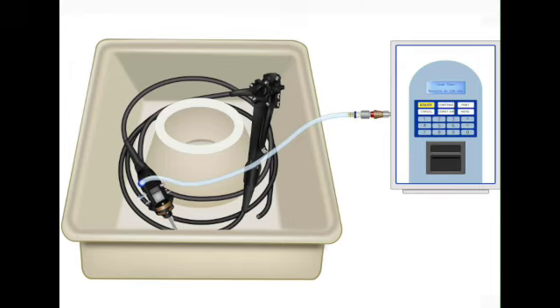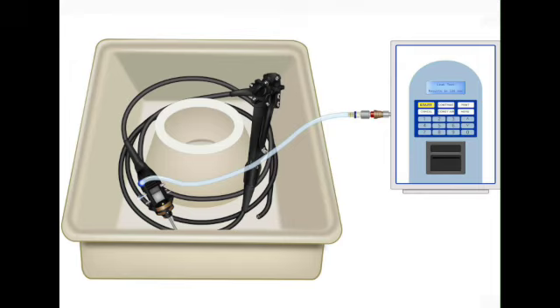Okay, seems straightforward enough. Well, here's a detail that often trips people up. It's about how you position the scope. Positioning? Yeah. If you put the scope in a small basin for the test, you have to be really careful not to coil it too tightly. Why would overcoiling be a problem? It's like kinking a garden hose. A tight coil can create these pinch points, and that can actually hide a small leak. The machine won't be able to detect the pressure drop properly. So it gives you a false pass. Exactly. A false sense of security.